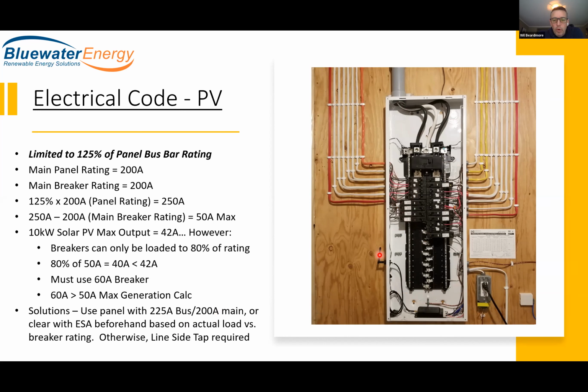What we have typically been doing is connecting the solar right down here on a double pole 50 amp breaker and or 60 amp breaker, depending on the size of the PV array, and then backfeeding through the panel, and any excess goes through the service conductors and then out to the meter. So that's how we've been doing it. Well, here's what code says. Code says that the maximum amount of generation we can backfeed onto a panel is 125% of the bus bar rating of the panel.